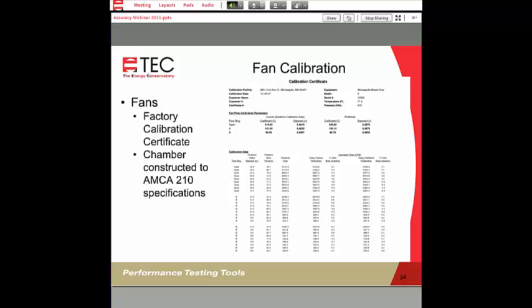And what happens is we now generate new coefficients and exponents that are entered into TechTite or TechLog to ensure that. Most, and I would say 99.5% of the users out there, do not need a special factory calibration. The standard calibration of our devices is sufficient for everyone.